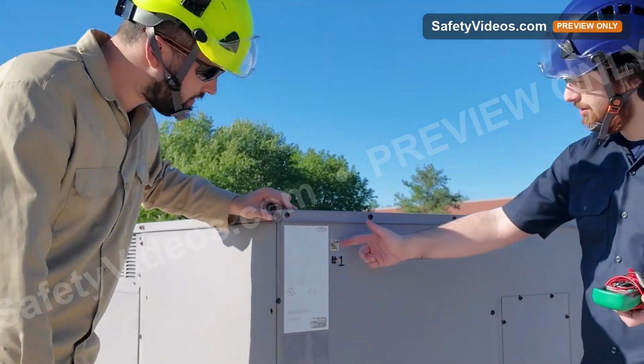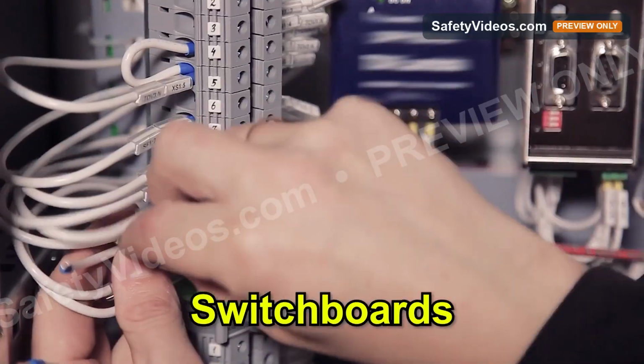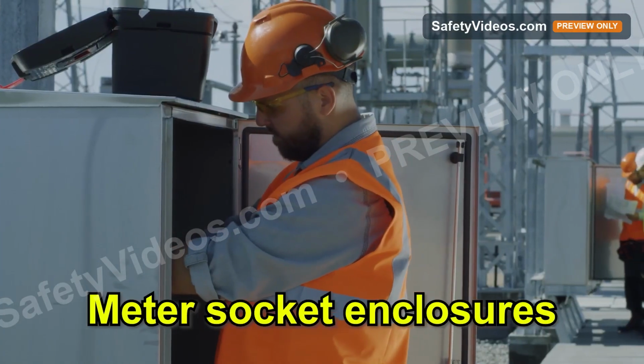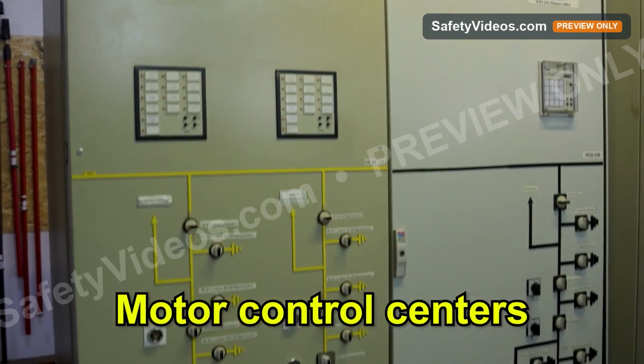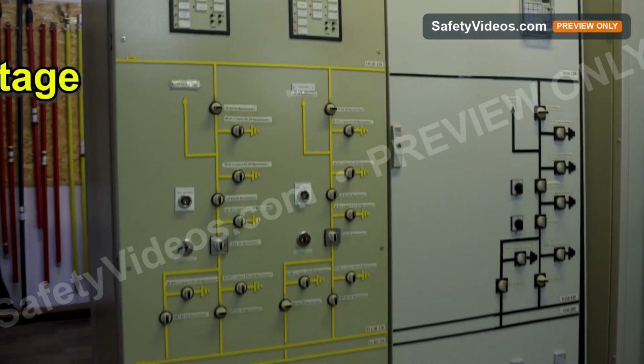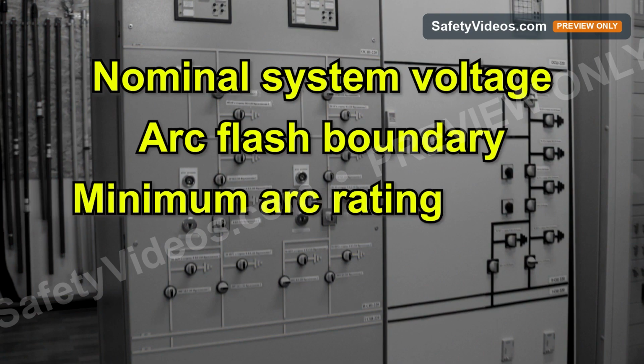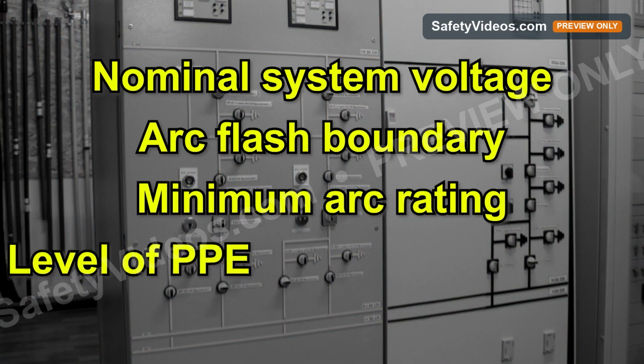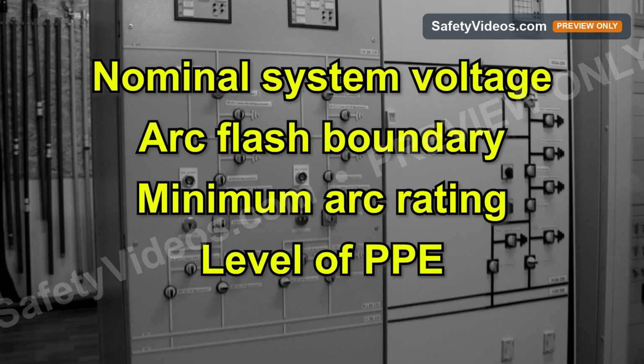All switchboards, panels, meter socket enclosures, and motor control centers should be labeled with their nominal system voltage, arc flash boundary, minimum clothing arc rating, and the site-specific level of PPE that should be used when working with them.